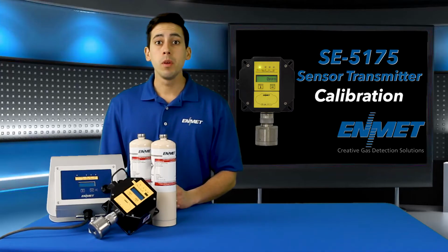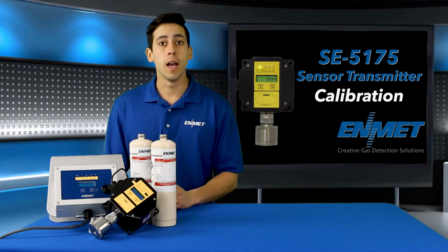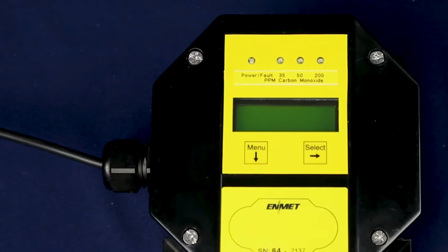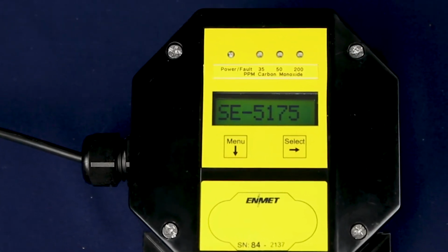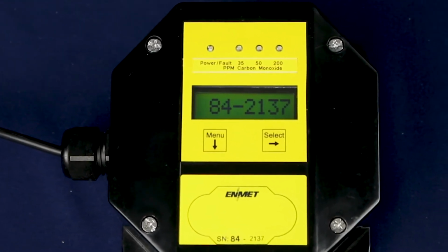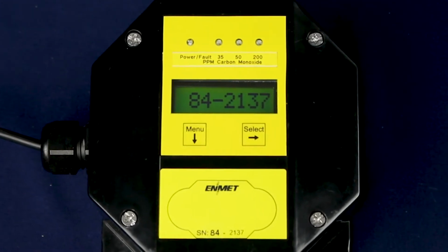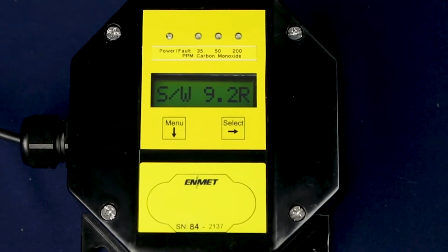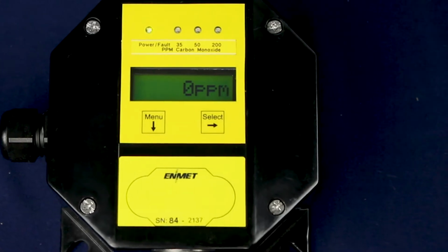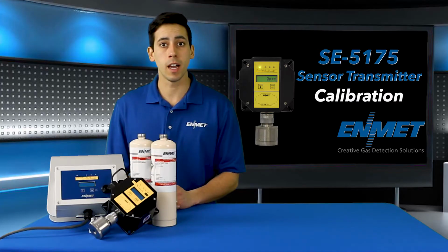In this video, I'll be walking you through how to calibrate ENMET's SE-5175 sensor transmitter. Make sure to wait 3 to 4 hours after initially supplying power to the SE-5175 instrument before an initial calibration. The SE-5175 has been pre-calibrated at the factory, and initial field calibration should result in only fine-tuning the circuit, as well as a way to check that the installation was successful.